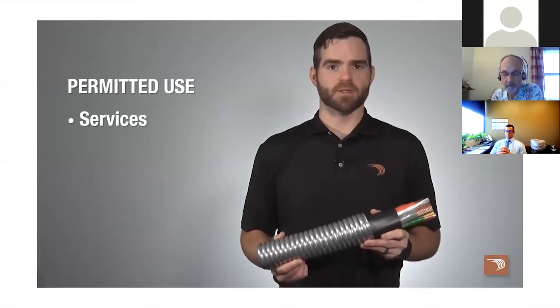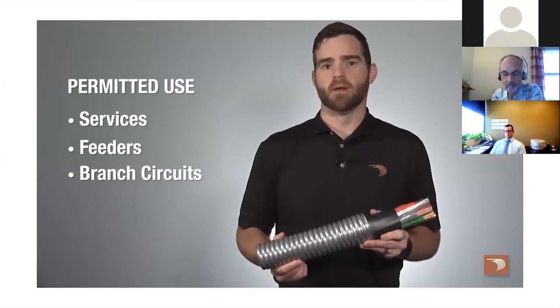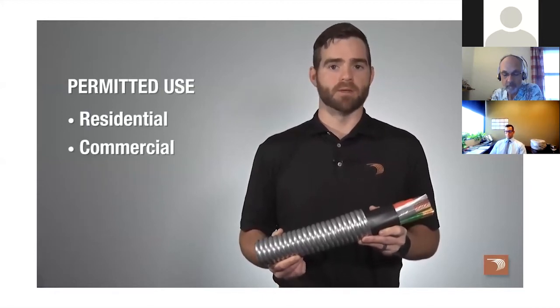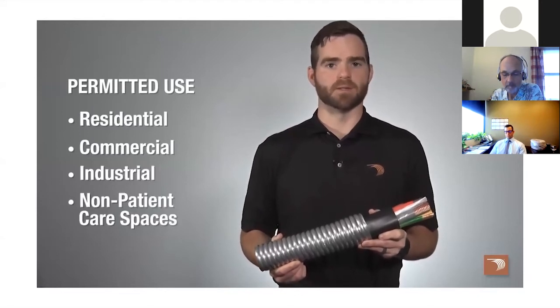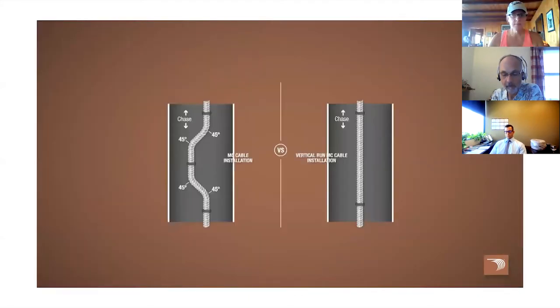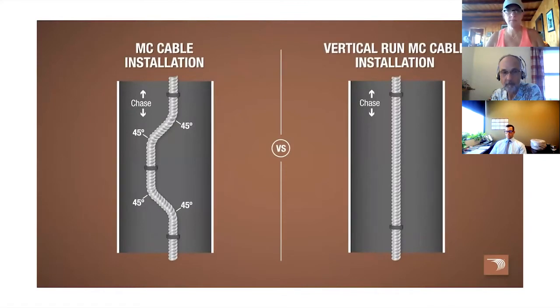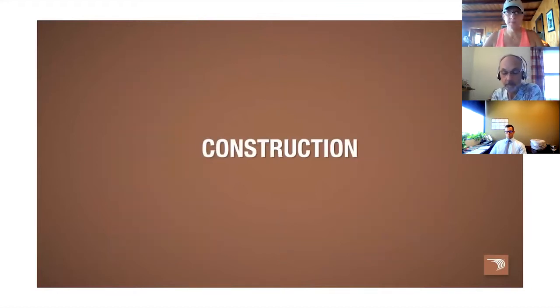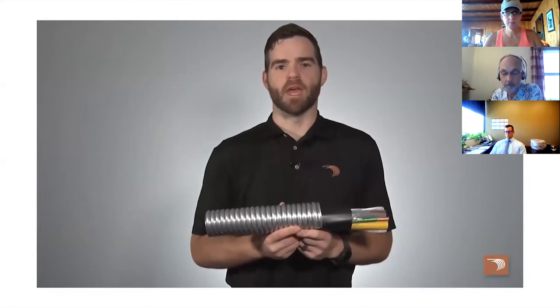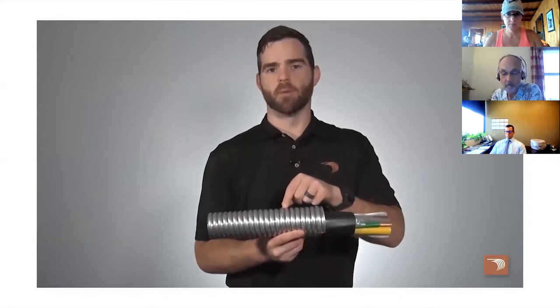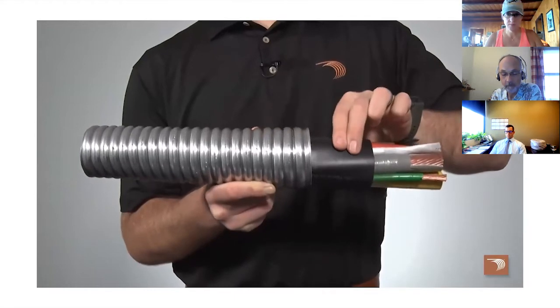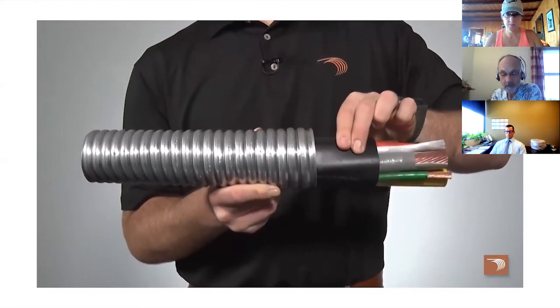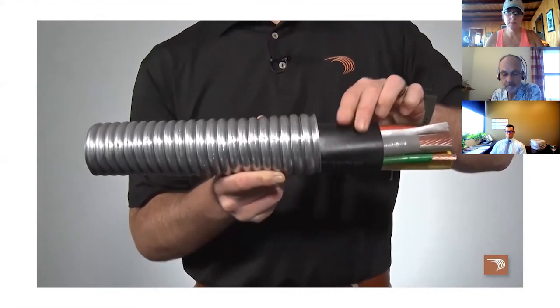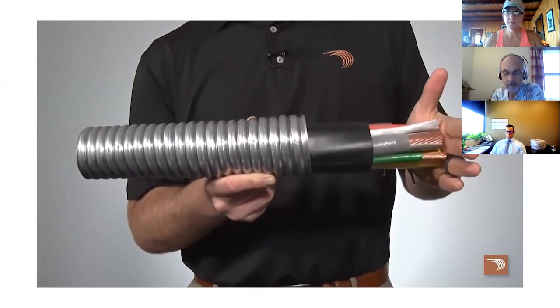It is permitted to be used for services, feeders, and branch circuits in residential, commercial, industrial, and non-patient care spaces within healthcare facilities. It was designed for use where offset space is limited or not feasible for installation, and eliminates internal conductor slippage on vertical installations. Vertical run MC cable is available in both aluminum and steel armor. It's constructed with a PVC binder layer under the metal-clad armor, which provides additional internal support to the inner conductors compared to traditional MC cable.